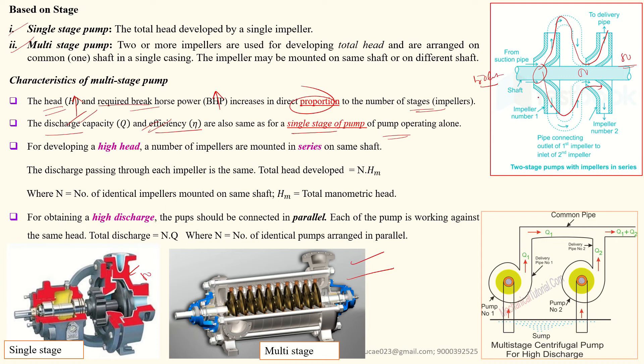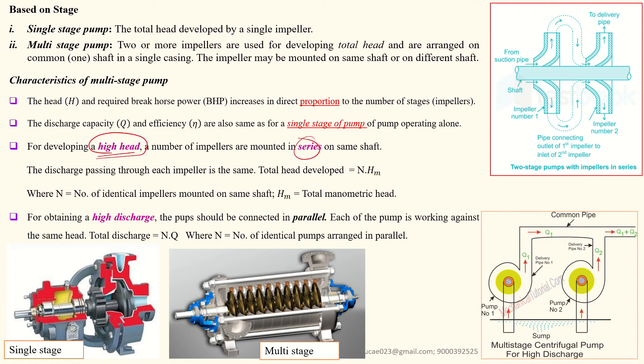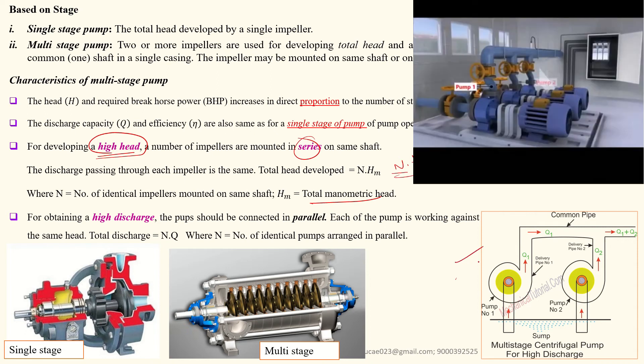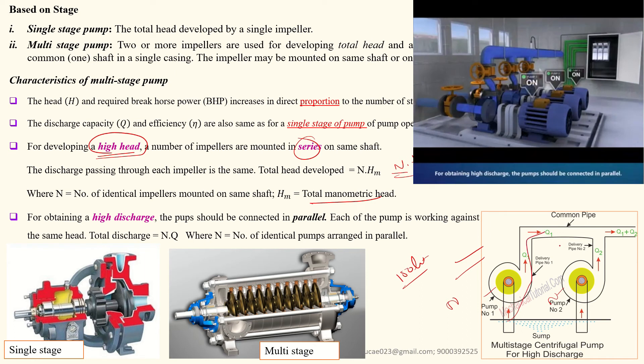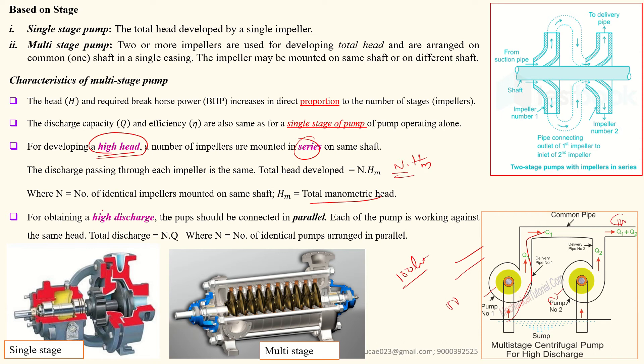So a multi-stage pump draws the same discharge as a single impeller, but achieves a much higher head. For developing high heads, arrange pumps in series — the total head is the number of impellers multiplied by the head per impeller. For high discharge, arrange pumps in parallel. If each pump draws 50 liters and two are in parallel, the total discharge is 100 liters.